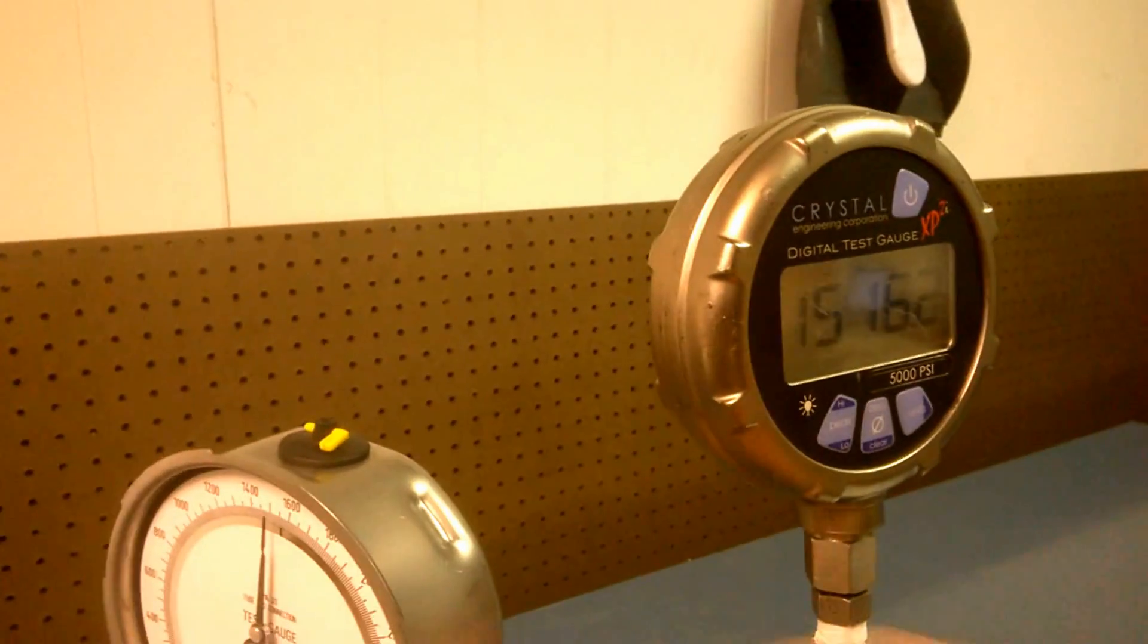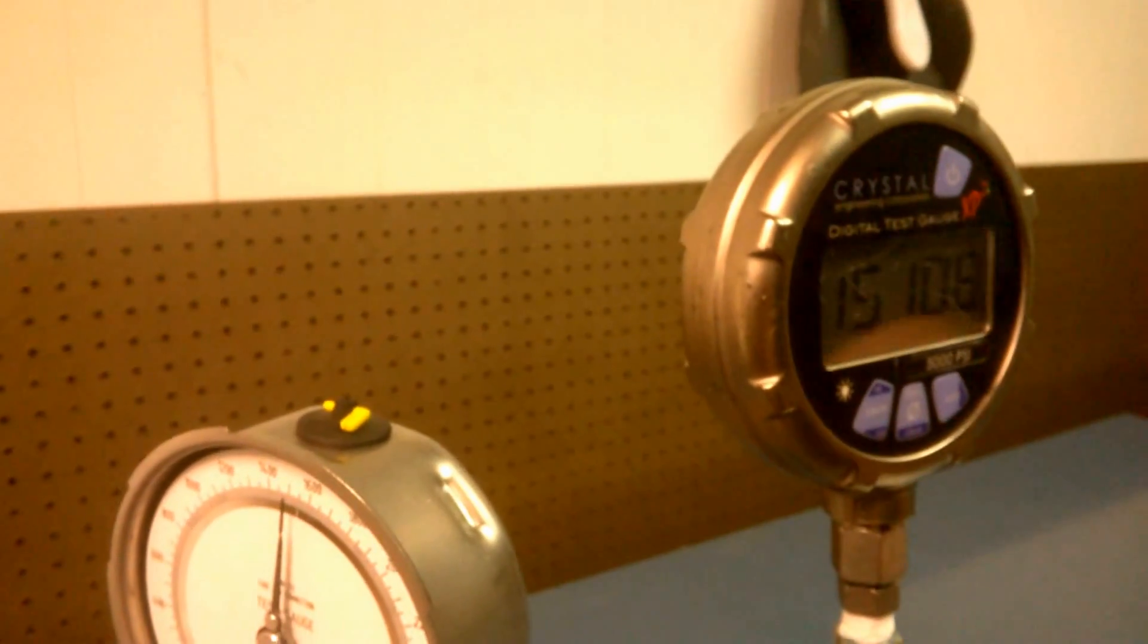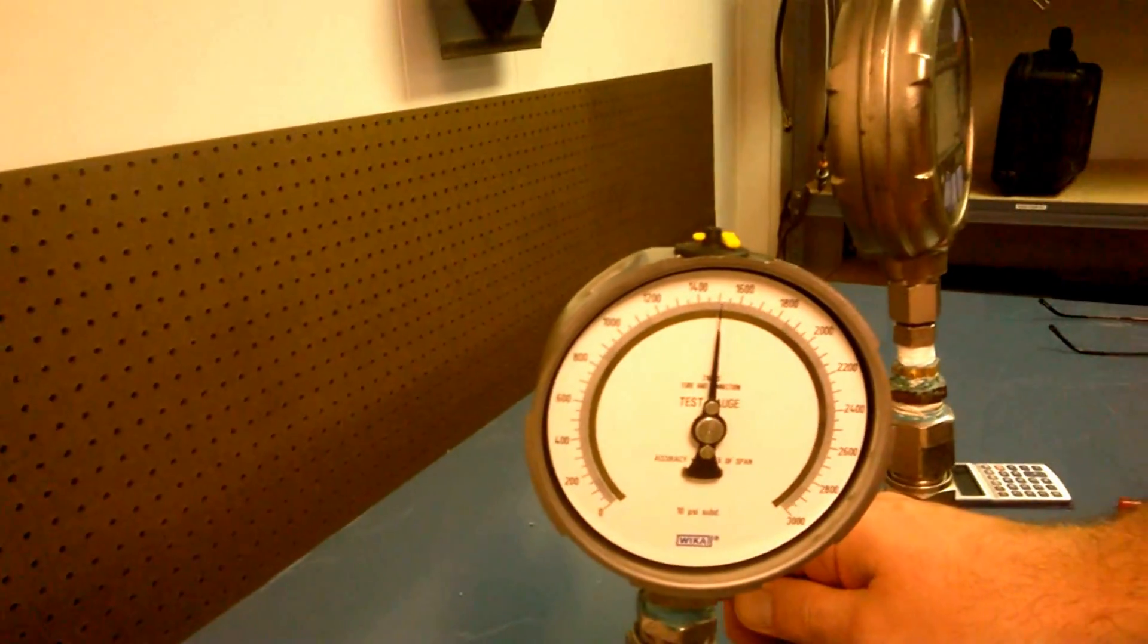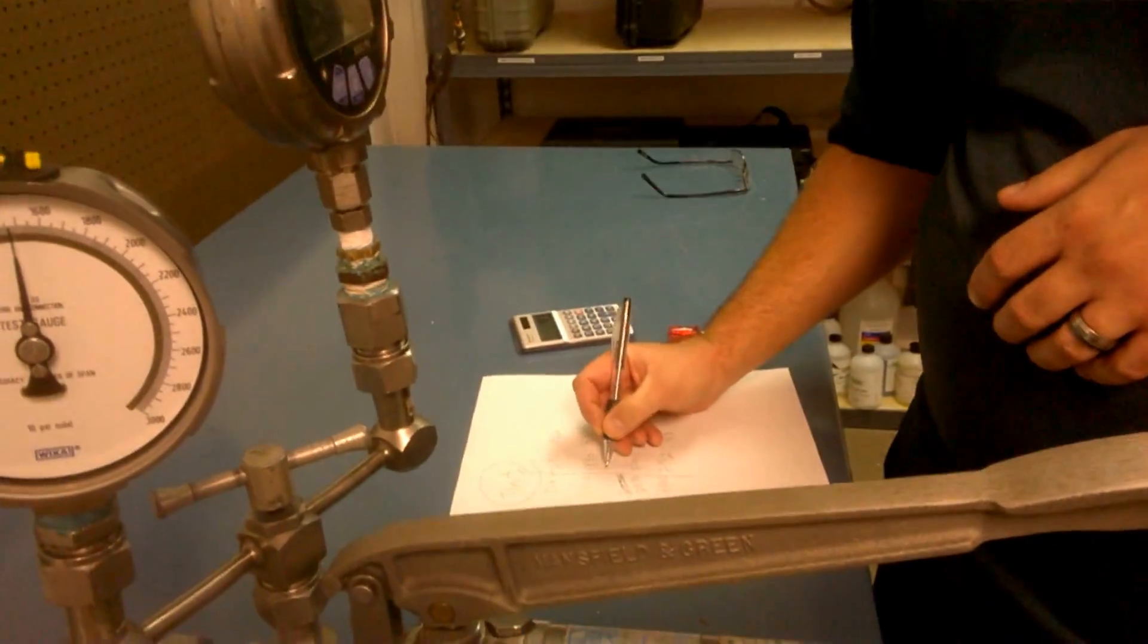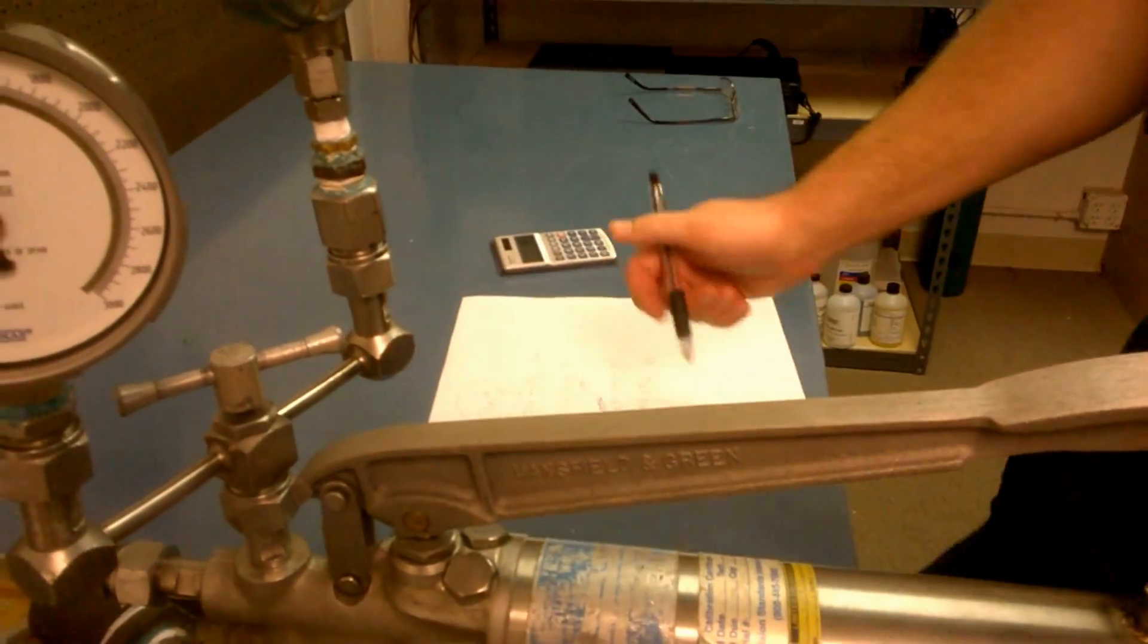We got a little leak somewhere. Let me tighten this. Of course, it starts leaking somewhere. 1499. So, that's 1 psi difference, which is well within the 7.5 psi.